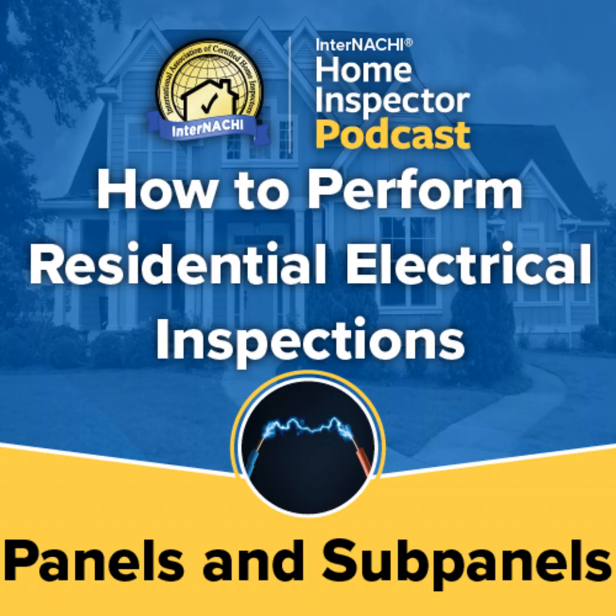Service panel board. A service panel board is a distribution or load center that contains the main disconnecting means, the main disconnect breaker, for example. This is the only panel where the neutral and grounds should be joined or bonded together.